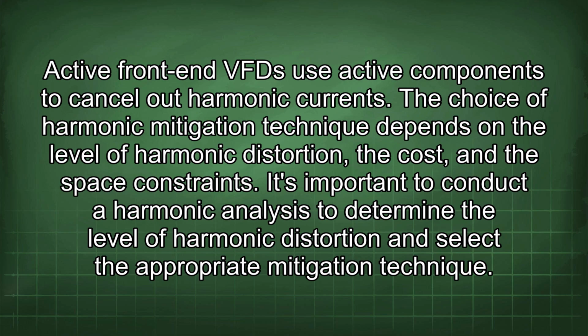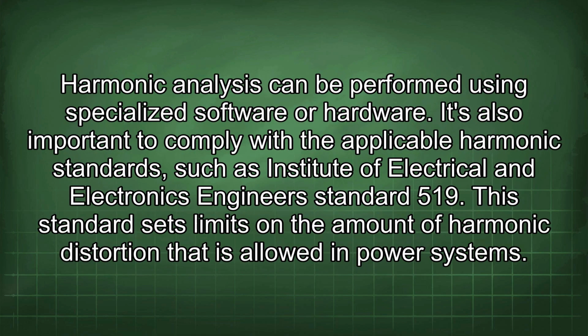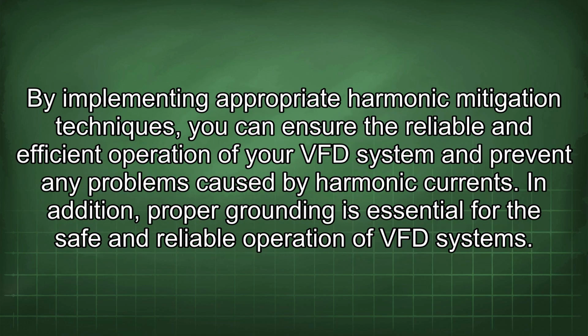It's important to conduct a harmonic analysis to determine the level of harmonic distortion and select the appropriate mitigation technique. Harmonic analysis can be performed using specialized software or hardware. It's also important to comply with the applicable harmonic standards, such as Institute of Electrical and Electronics Engineers Standard 519. This standard sets limits on the amount of harmonic distortion that is allowed in power systems. By implementing appropriate harmonic mitigation techniques, you can ensure the reliable and efficient operation of your VFD system and prevent any problems caused by harmonic currents.